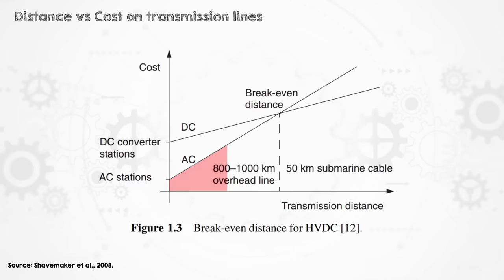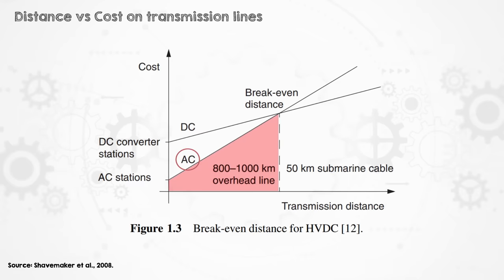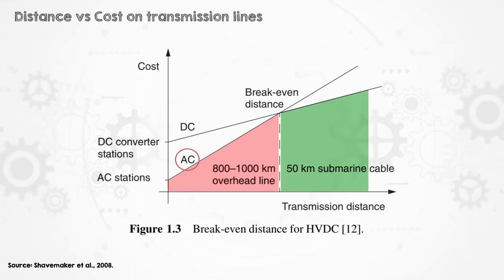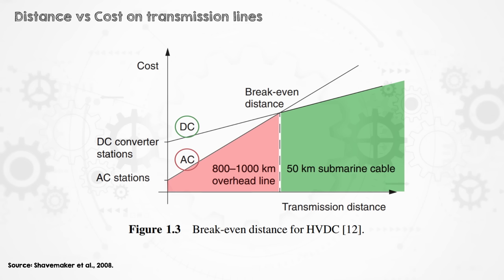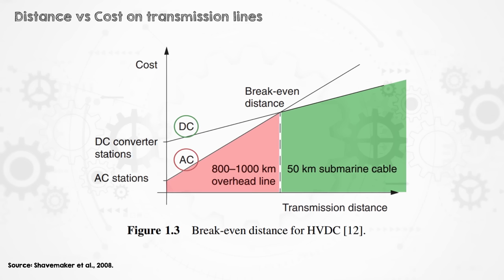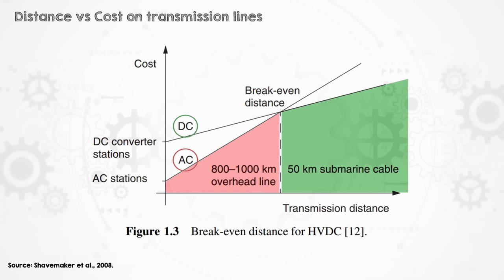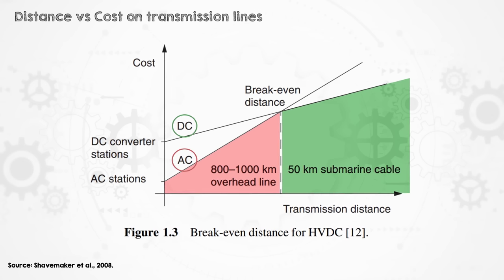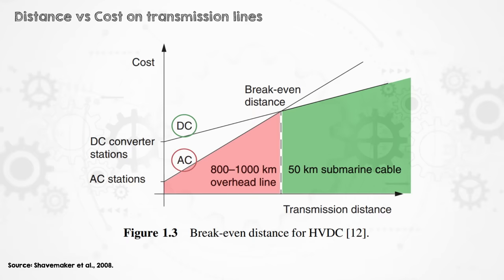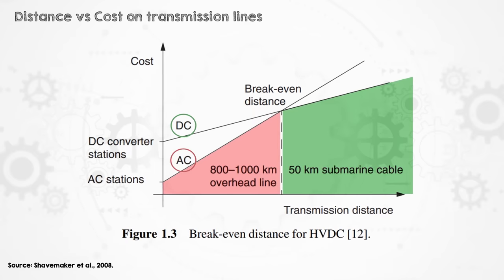For short distances, AC still wins due to its cost-effective infrastructure. However, for longer distances, power losses dominate, and DC systems are cheaper due to their higher efficiency. There's a break-even distance somewhere around 500 to 900 kilometers for overhead lines, beyond which HVDC becomes more economical than AC. And for underground or subsea interconnectors, that distance is much shorter because the capacitance effect is more of an issue when the cable is so close to the ground or water.